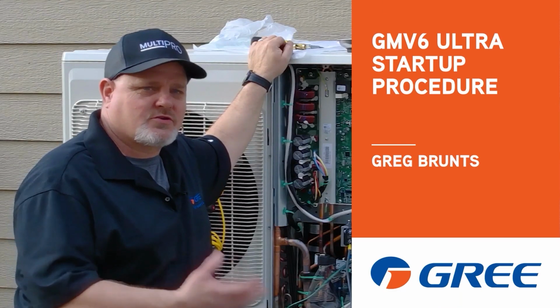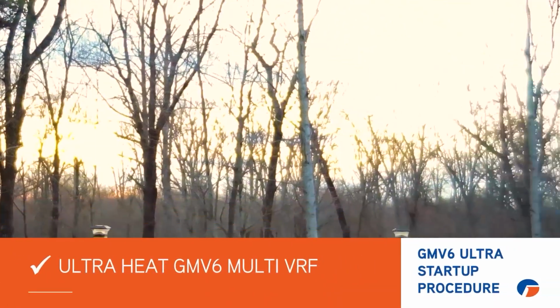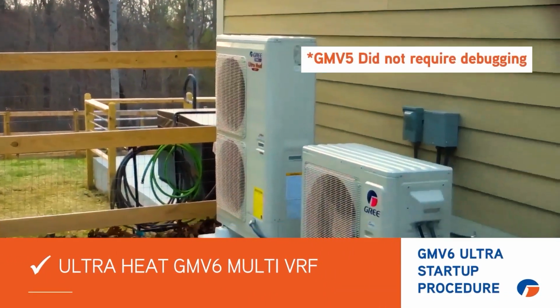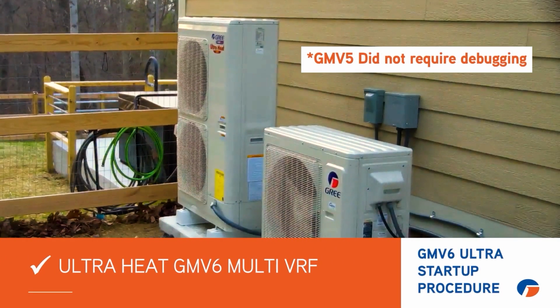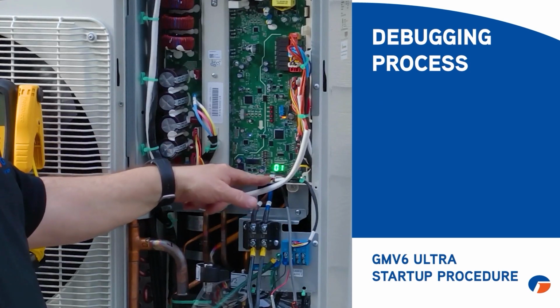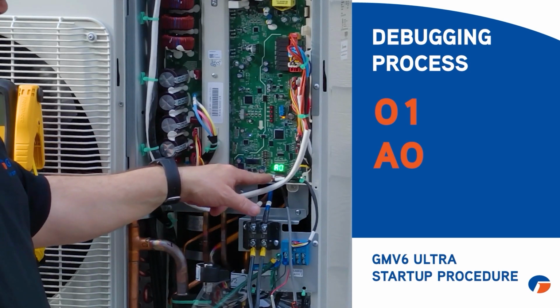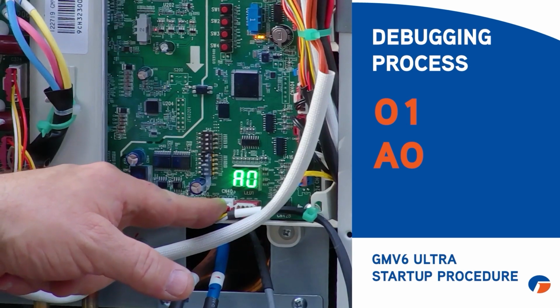Wanted to show you the proper startup procedure for the new GMV6 Ultra. The predecessor, the GMV5 Ultra, you didn't have to put through a debug process. This machine you do. As you will see on the display here, it's saying 01, then AO, and it goes back to 01, goes to AO. It's not an error code, it's just that you're ready for debug.